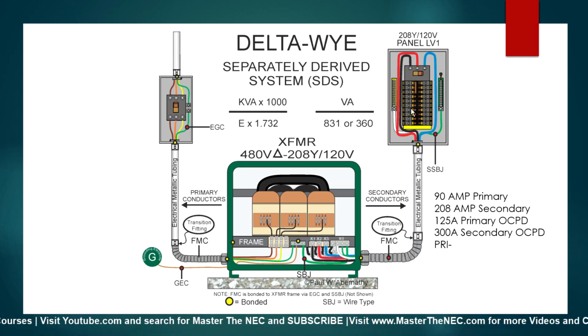Well, because you could have different loads in here. And these conductors are good for 300 amps, but it would be pointless because this transformer can only put out 208. So that's why it's important to understand that possibly I can use the 125 here, and this right here could be simply based on the load necessary. Remember, it can go up to 125% even if it was secondary protection, but it doesn't have to be, okay? But it at least has to be 208 amps, because we know that this transformer could potentially put out 208 amps.